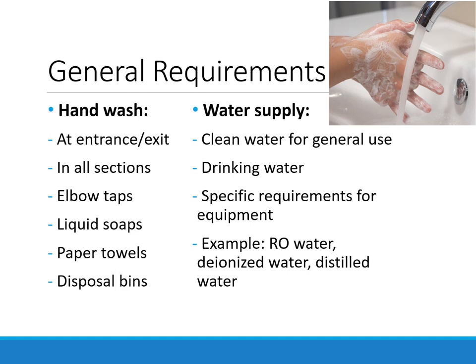Water supply: there must be three kinds of water supplied in the laboratory. The first is clean water for general use, with a continuous supply for use in the laboratory, in the washing and cleaning areas, and in the toilets. The second is drinking water. The third is special water as per the specific requirements for equipment, such as RO water, deionized water, double deionized water, and distilled water.